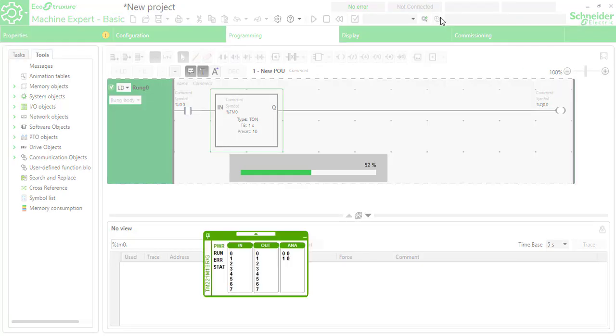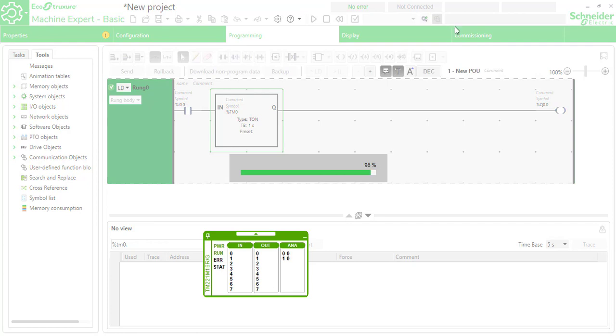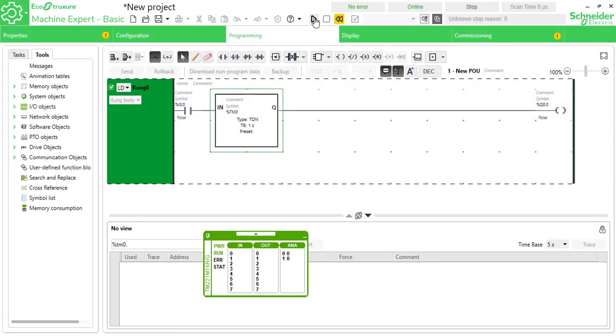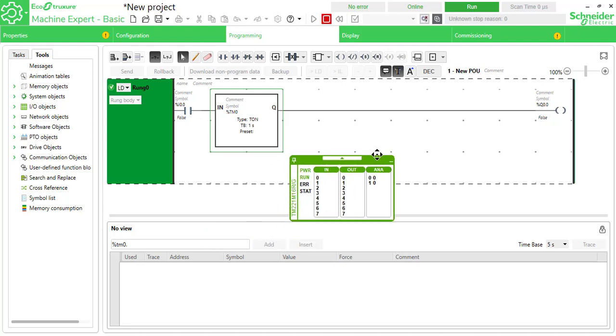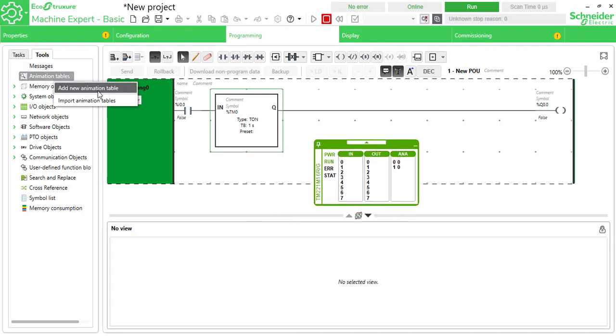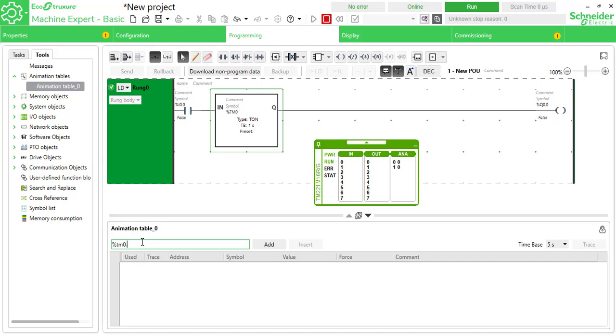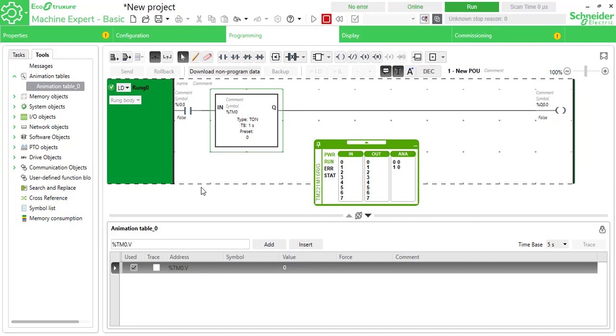Launch the simulator, go to runtime, and start the controller. To watch the timer value, go to the animation table, add a new animation table, and add %TM0 and %TM0.V — the preset time — to the watch list. Run the controller. I0.0 is the contact powering the timer. You can see the timer start running: one, two, three... with preset of 10 seconds, after 10 seconds you'll get the on-delay output.